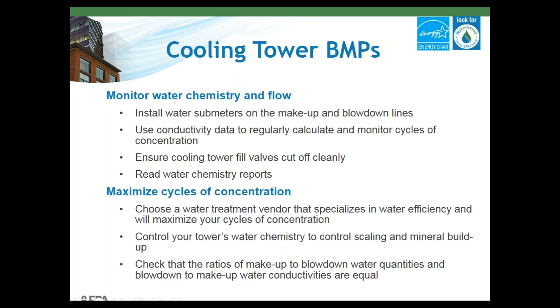One great thing to consider is using air handler condensate recovery for your cooling tower as makeup water. Air handler condensate is a great alternative source because it's free of minerals and total dissolved solids, and it's cooler than ambient air. Condensate is typically drained into the sewer or storm, but since it's generated in highest quantity when the load on your cooling tower is highest, it's a great source of cold, clean water, because as you need more cooling in your building, your cooling towers need to ramp up.